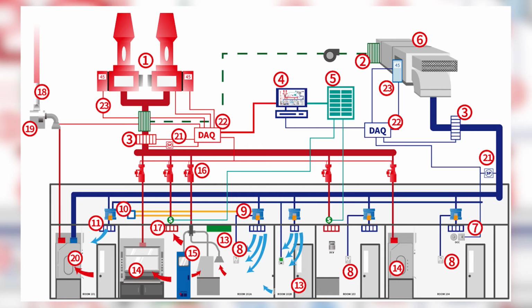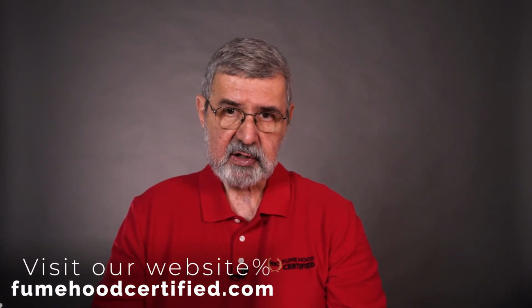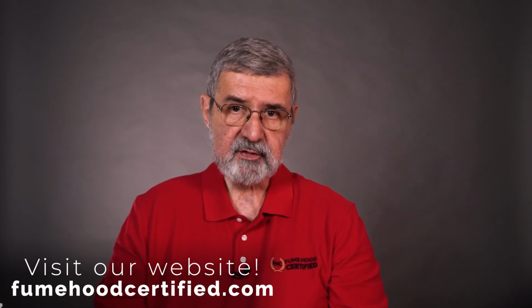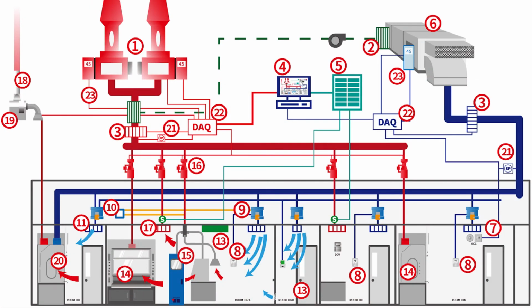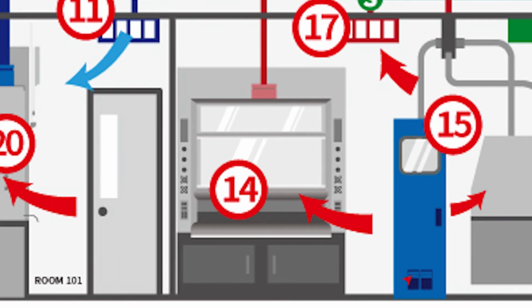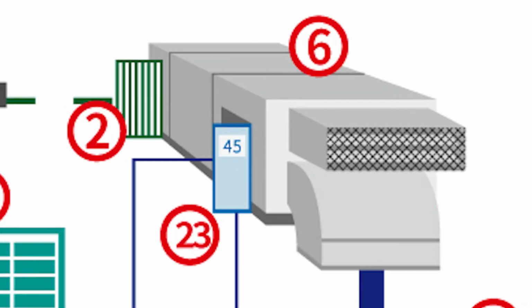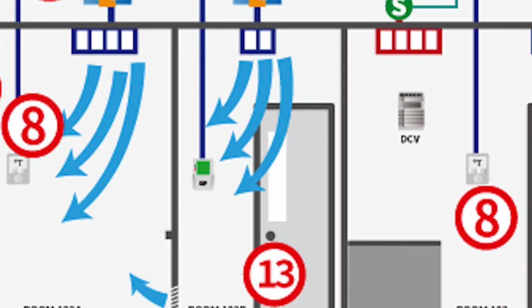How often do they check the fire sprinkler system in your building? A laboratory ventilation system is much more complex and just as important. Shouldn't the ventilation system be inspected as frequently? With a fire sprinkler system, you generally only see the sprinkler heads in the lab. You don't see all those pipes, controls, and pumps that make it work. The same is true with the laboratory ventilation system. All you see is the fume hood itself. You don't see all the things above the ceiling and on the roof that are necessary for the hood to work correctly.